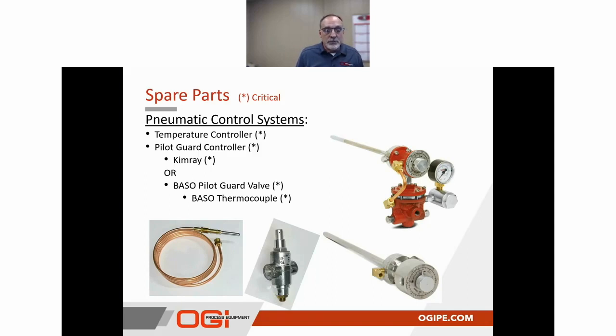Pilot guards: there are two different approaches taken on pilot evaluation or flame sensing, and that would be the Kimray pilot guard shown in the lower right-hand side, or the BASO pilot guard valve. In looking at the operation of a heater, the pilot is obviously the most critical operation. I realize there are things associated with the bath and regulation and these other things, but if your pilot isn't working or isn't reliably being sensed, then your heater literally is down.